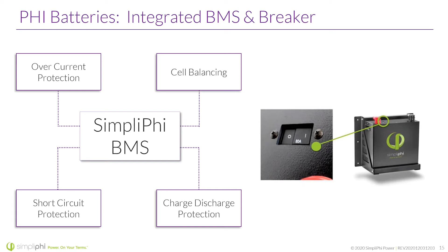Okay, before we get into all that, let's talk about some more key features. C/2 rating, what does that mean for us here at SimpliPhi? Well, a C rate is a measure of the rate at which a battery is discharged relative to its maximum capacity. So we can look at C rating as, hey, this is the rating at which the battery gets its amp hour rating. So our 3.8 kilowatt hour battery has a rating of 3.8 kilowatt hours, or 75 amp hours. Again, that's the rating. We rate that at C/2.